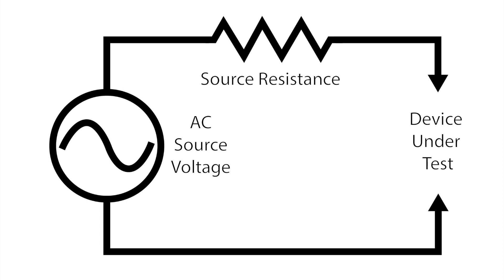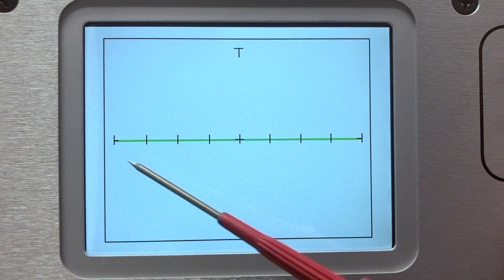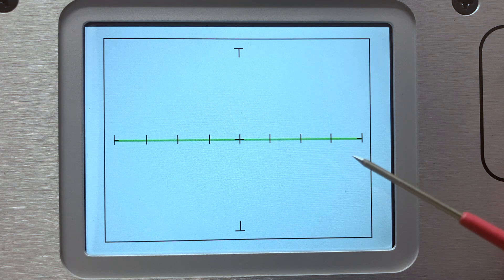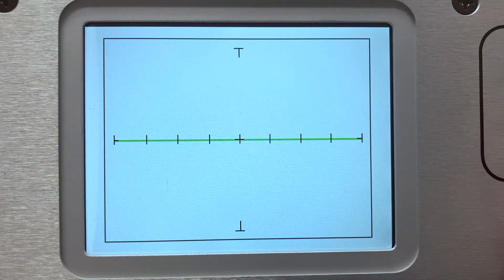A simple analogy would be to think of a Huntron tracker as a visual AC ohmmeter. The horizontal axis on the display represents voltage. An open circuit signature will be a horizontal line since we have maximum voltage across the points under test.